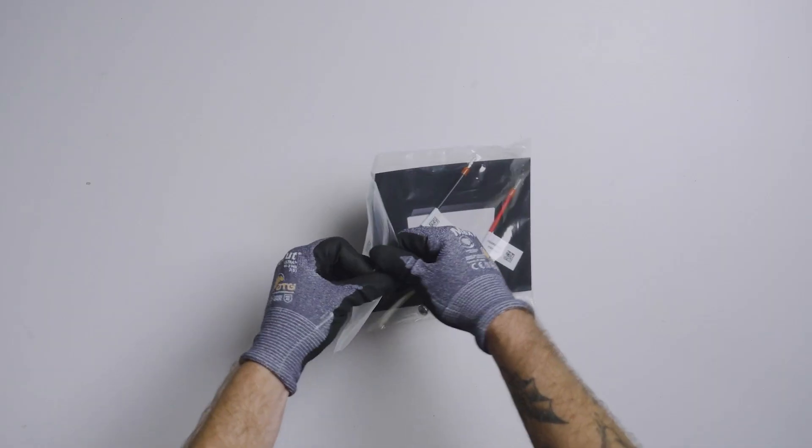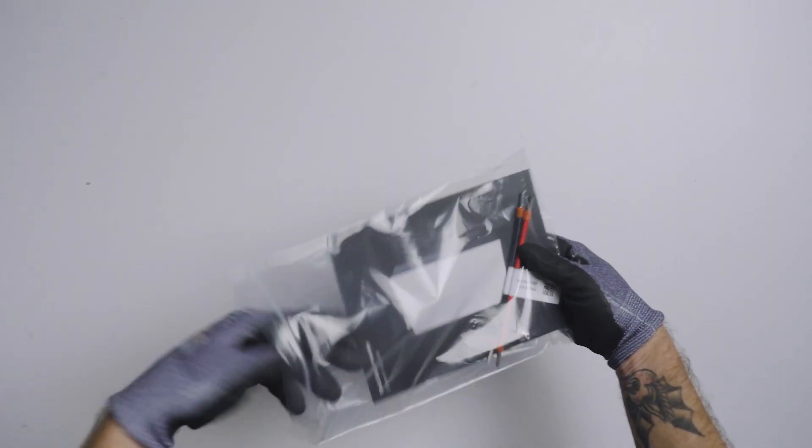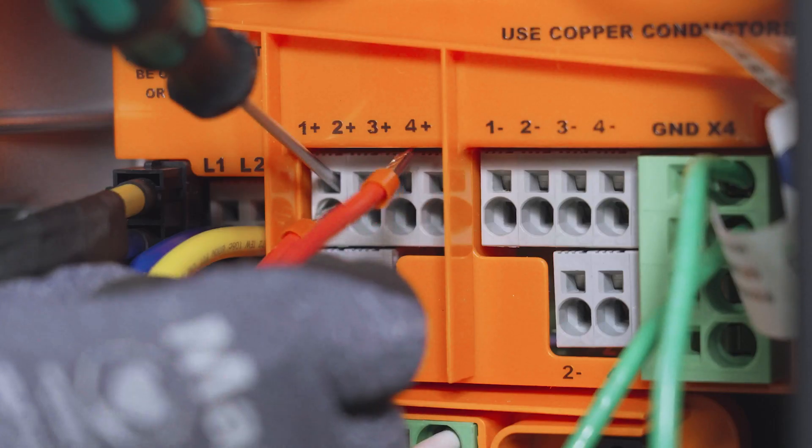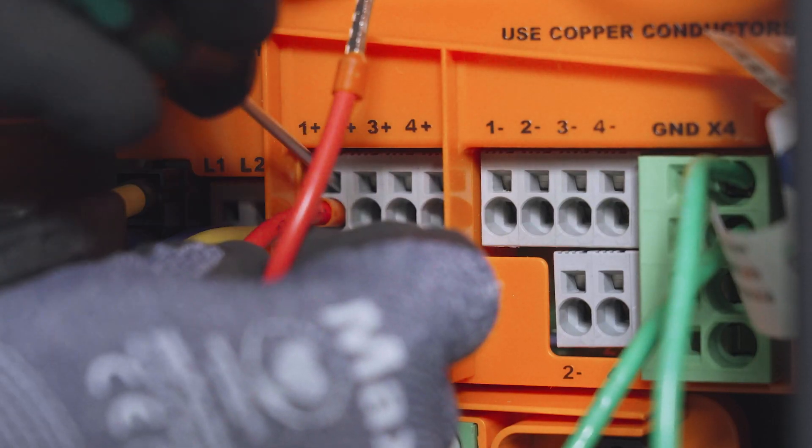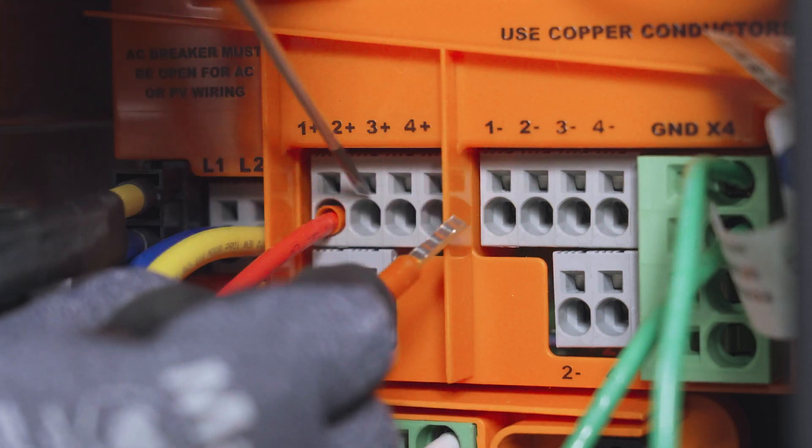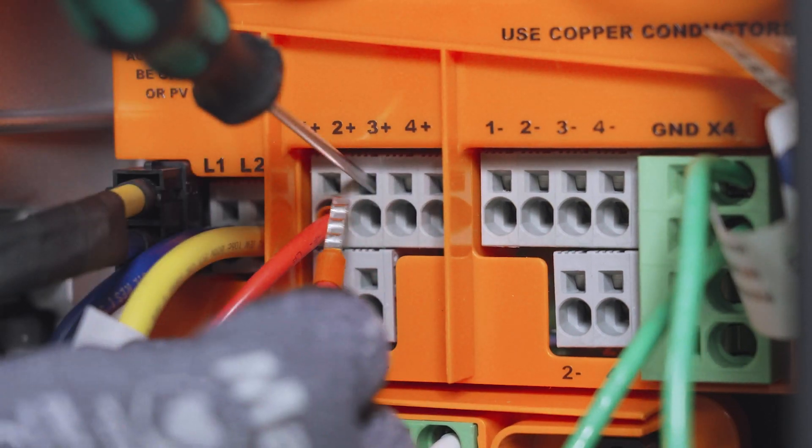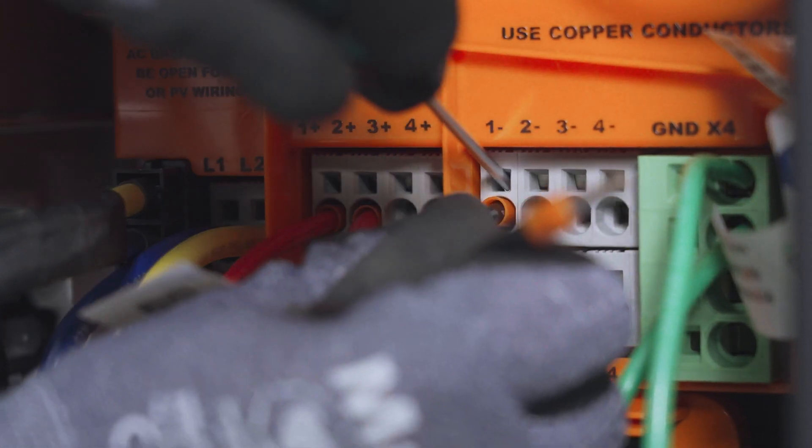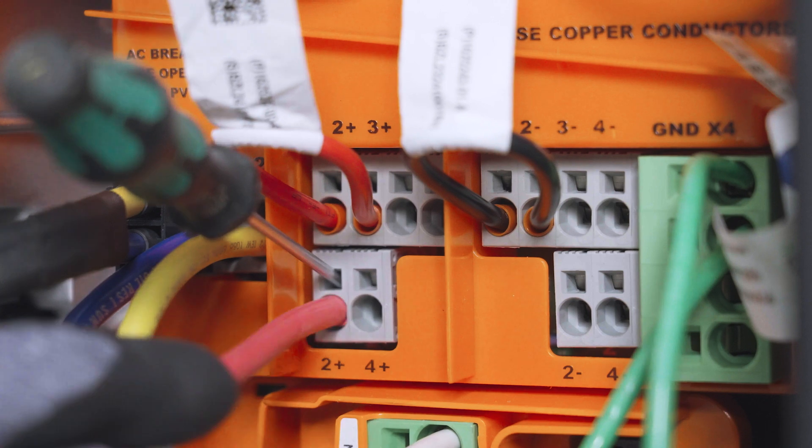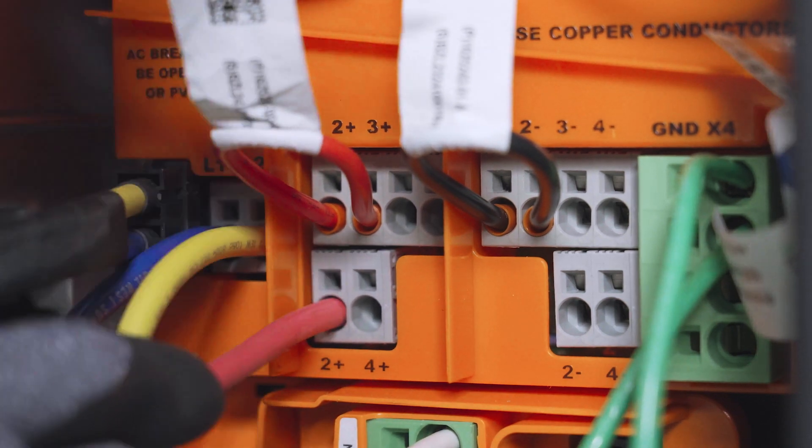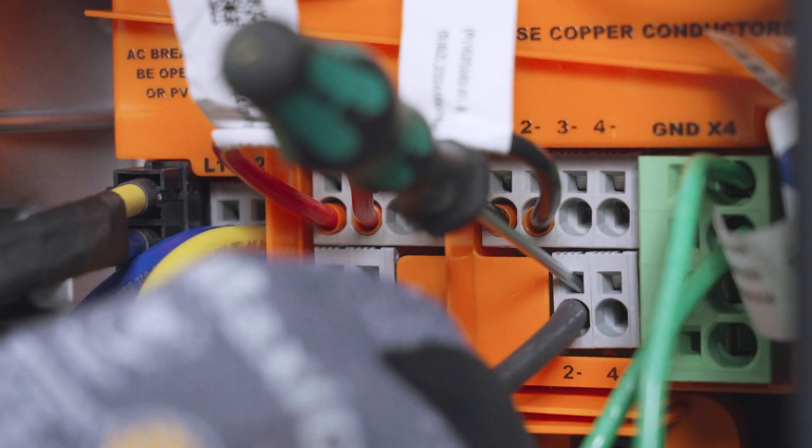Follow the same steps to terminate one jumper between positive 1 and positive 2 on this top row of terminals. Then install another jumper to connect negative 1 and negative 2. Finally, terminate the positive and negative DC conductors on this lower row of terminals, labeled positive 2 and negative 2, to complete the high amperage circuit.